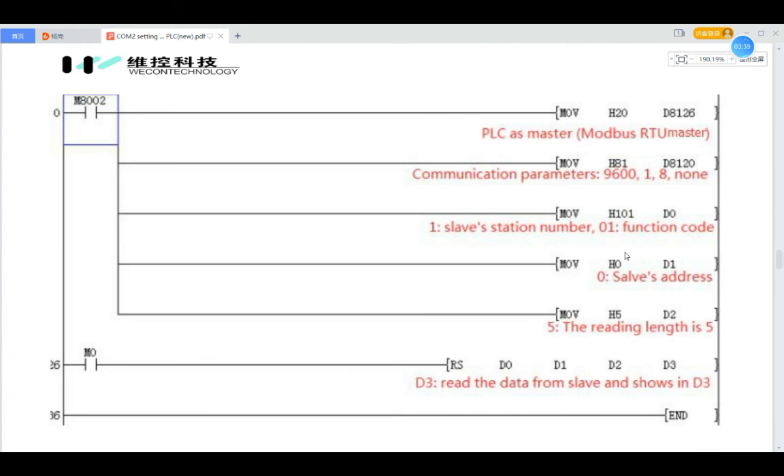In this demo the slave station number is 1 and the function code is 01, so we move H101 to D0. About the function code: 01 means read bit address, 03 is used to read word registers, and so on. The start address we set to H0, and we move H0 to the corresponding register. The reading length is 5. Then we need to use the RS instruction to read the data from the slave. The RS instruction needs to know the slave station number and function code as the first value, the slave address as the second value, and the reading length as the third value. The RS instruction will then show the value in D3.